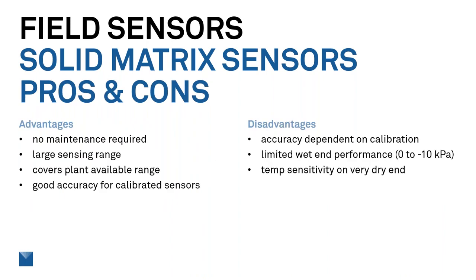With solid matrix sensors, there are advantages and disadvantages. One main advantage is there's no maintenance needed. Most solid matrix sensors also have a relatively large sensing range, typically between -10 and -2500 kilopascals, covering the plant available range. If calibrated, you can get really good accuracy without any maintenance. The disadvantage is that the accuracy is dependent on calibration.